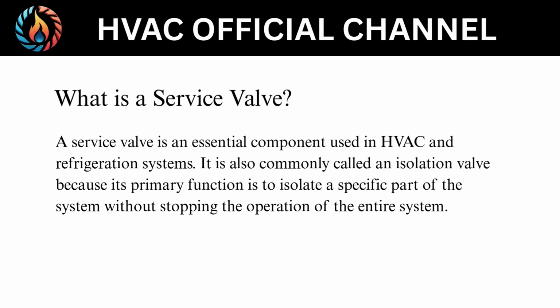What is a service valve? A service valve is an essential component used in HVAC and refrigeration systems. It is also commonly called an isolation valve because its primary function is to isolate a specific part of the system without stopping the operation of the entire system.